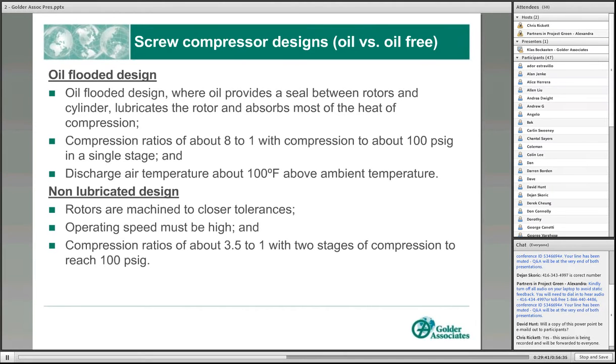In the non-lubricated style of screw compressor, the rotors are machined to much closer tolerances and operate at a greater speed. But the compression ratio you can reach with a non-lubricated design is lower, typically 3.5 to 1. So a typical screw compressor delivering 100 psig would have 2 stages of compression, so 2 sets of screws, to reach the typical air pressure of 100 psig.